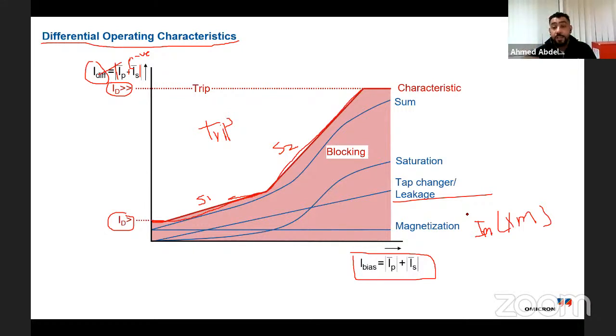The second and the most important error is saturation. Because we said that maybe I have a fault very close to one CT, and this CT will be saturated, and the other CT on the high voltage side is not saturated because there is a load in between the fault and the CT. This saturation can lead to a misoperation of the differential protection. So what I need to do is stop the relay from operating in case of saturation.